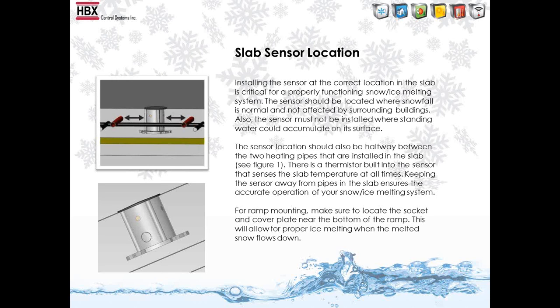Installing the sensor at the correct location in the slab is critical for proper functioning of the snow and ice melting system. The sensor should be located where snowfall is normal and not affected by surrounding buildings. The sensor location should also be halfway between the two heating pipes installed in the slab. There is a thermistor built into the sensor that senses the slab temperature at all times. Keeping the sensor away from pipes ensures accurate operation.